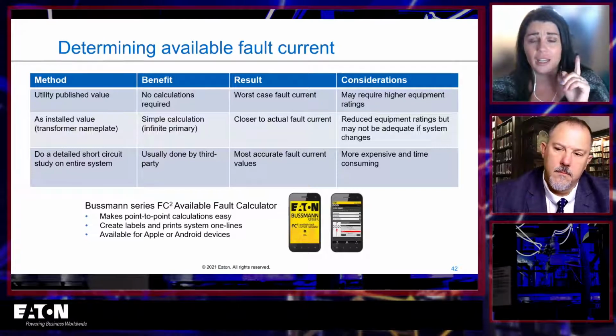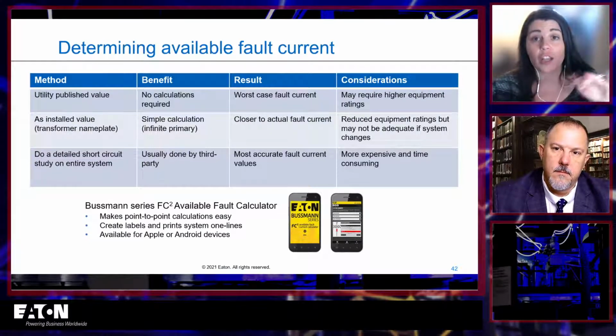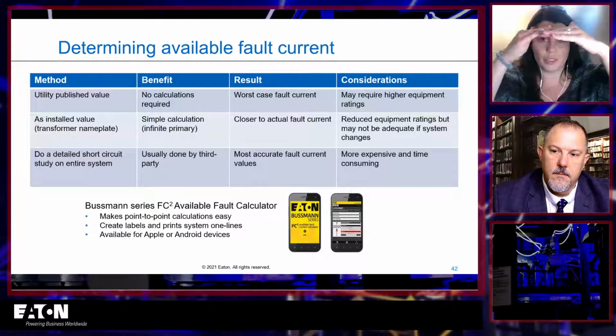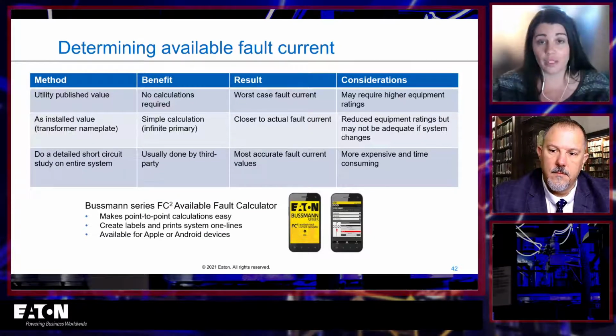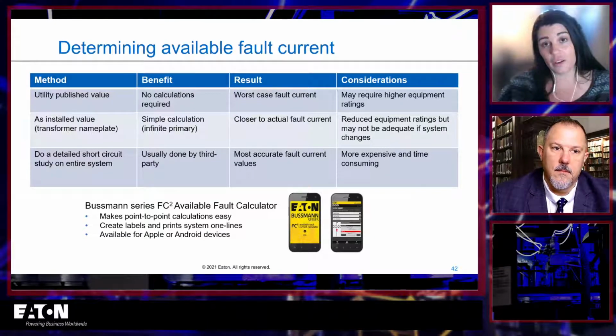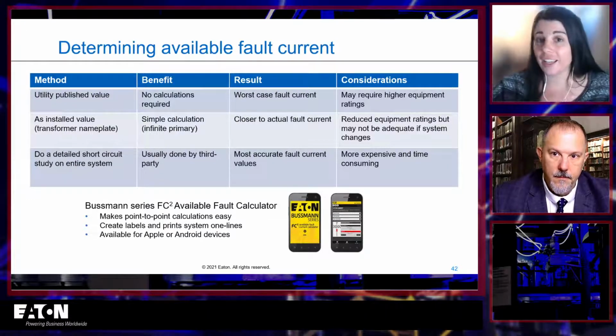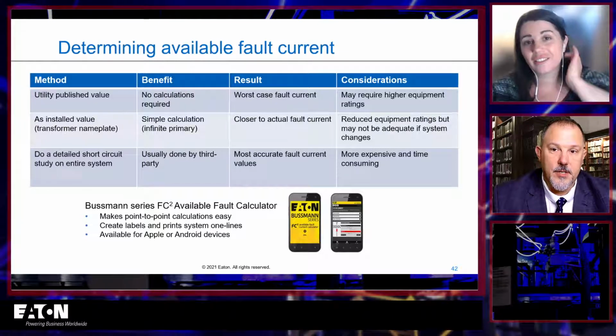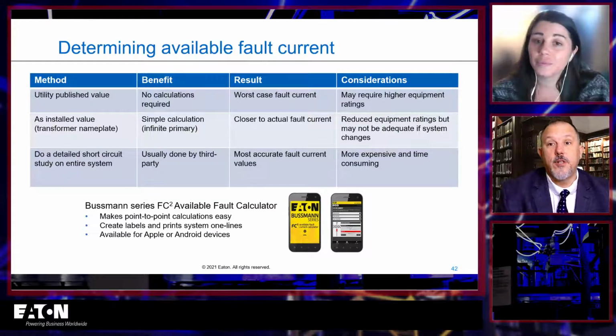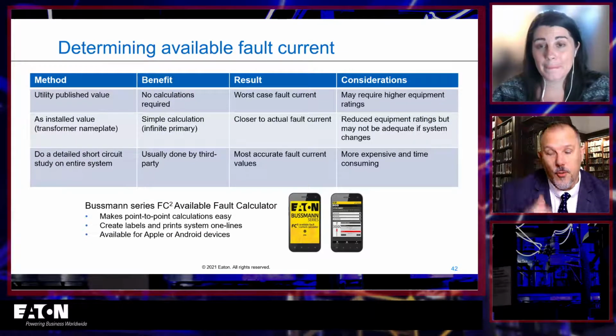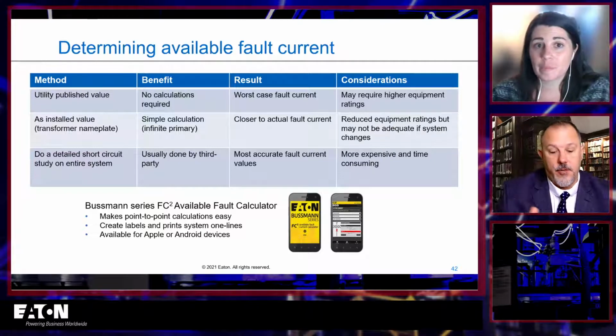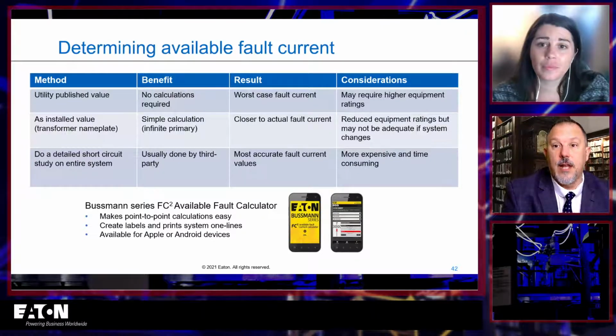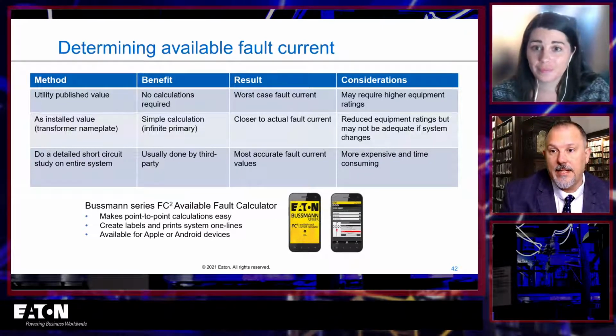And then you can also print out the documentation piece. So it'll say you built up your system, and it'll give you a nice little PDF. Here's your system. Here's the fault current calculations. Something that an inspector, I think, would gratefully take as documentation. Absolutely. And it meets the code, because remember, the code wants you to document how. The one-line diagram will let the inspector see the conductor that you use and the length that you use, because you have that little one-line diagram.